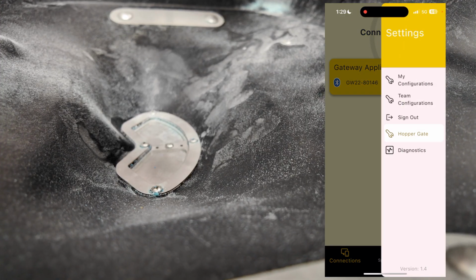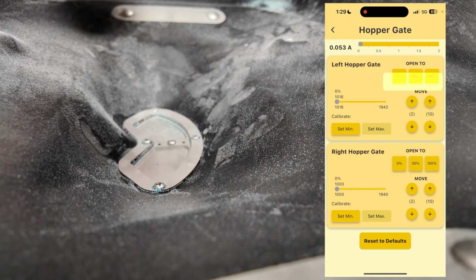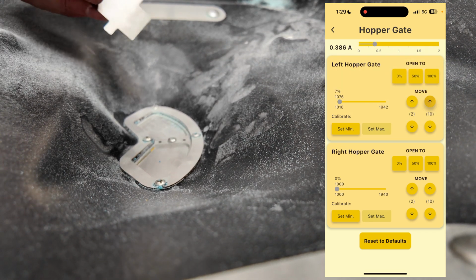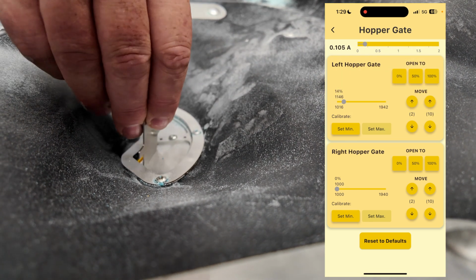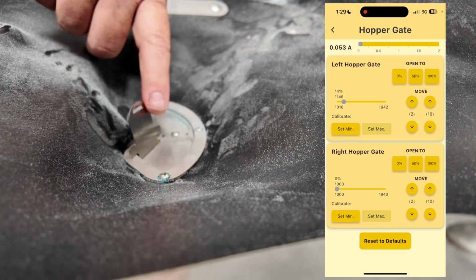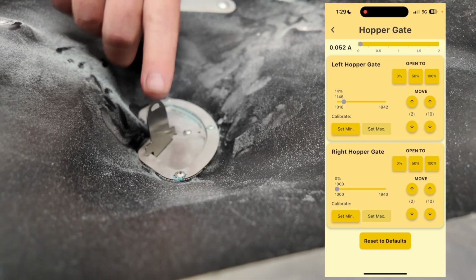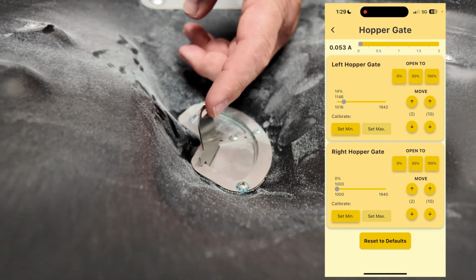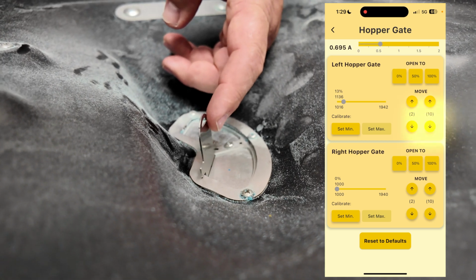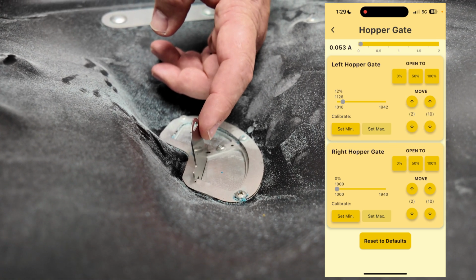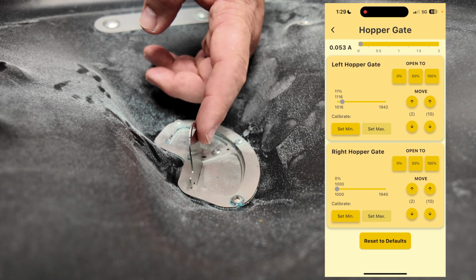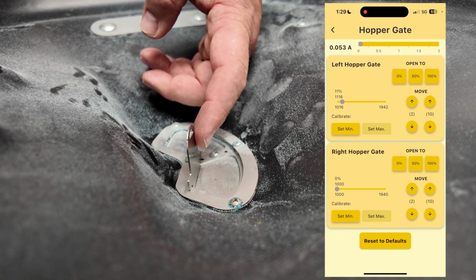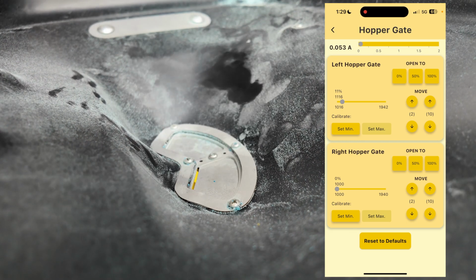Select the gear, go to hopper gate, and start opening the left servo. Place my calibration key in the gap. You can see this moves forward and back. Press slightly forward just to hold it up, and I'll start closing the gate using the app, doing -10, then -10 again. I want this straight up and down, with very light pressure, which it is. So now I have the min set.